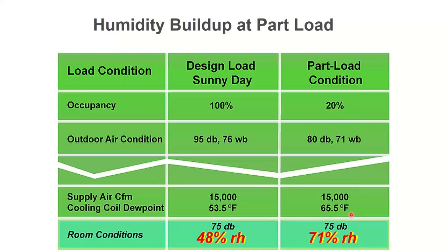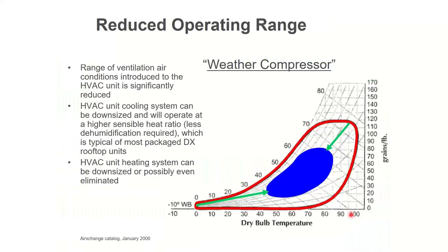Modulating chilled water valves, slowing blowers down, all kinds of things we can do there. Humidimizer, hot gas reheat, lots of options. One of those options is the ERV, especially if my humidity problem is coming from the outdoors. If it's mostly indoors, right, it's a gym where people are working out like madmen and sweating it up, well, then the ERV is not going to help me as much as maybe one of the other methods would with modulating chilled water or something like that.